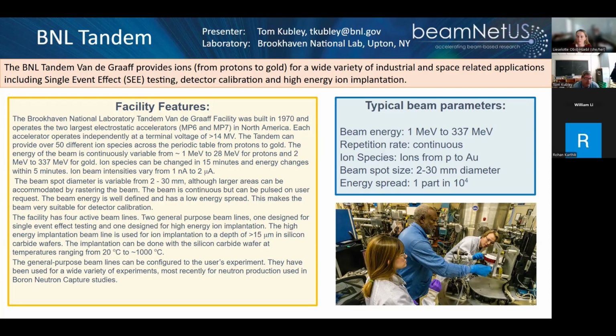Specifically, we have been doing a lot of silicon carbide implantations with that, but anything that needs to be implanted, we can. That actually has a temperature control on it, so we can go up to about 1,000 degrees C. We're also capable of running below 0 temperatures, so if you need to do an implantation cold or hot, we're able to do that. Since we're electrostatic, we provide a continuous beam. If you need to have pulse for some reason, we can pulse it down to a few microseconds. Because of our energy spread being so small, 1 part in 10 to the 4th, we are really good at doing detector calibrations.